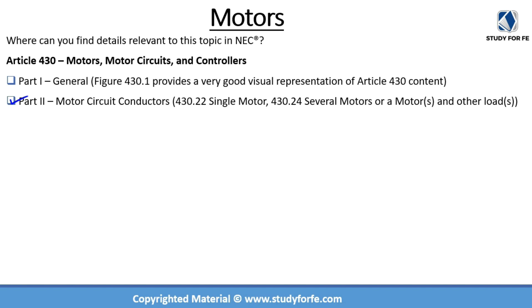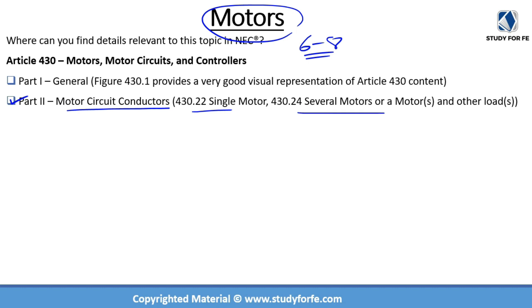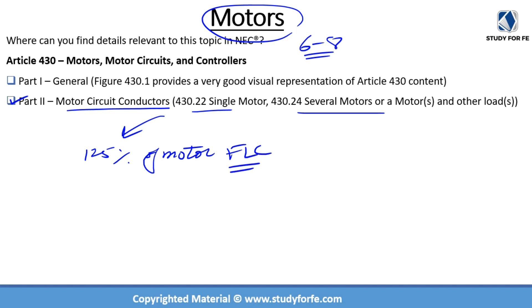Part 2 of Article 430 is titled Motor Circuit Conductors. Motors are unique in that they are almost completely inductive in nature with very low resistance, resulting in a very high inrush current — typically 6 to 8 times their full load current. I would like to draw your attention to two sections: 430.22 and 430.24. Section 430.22 deals with single motors, and the gist is that for a motor in continuous application, the conductor should not be sized less than 125% of motor FLC.